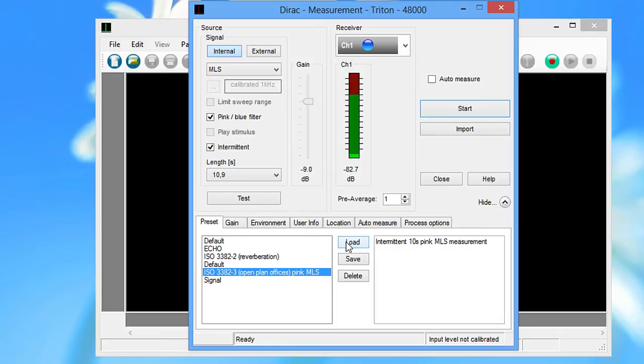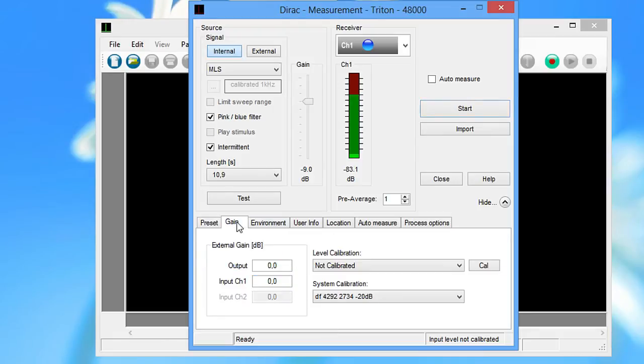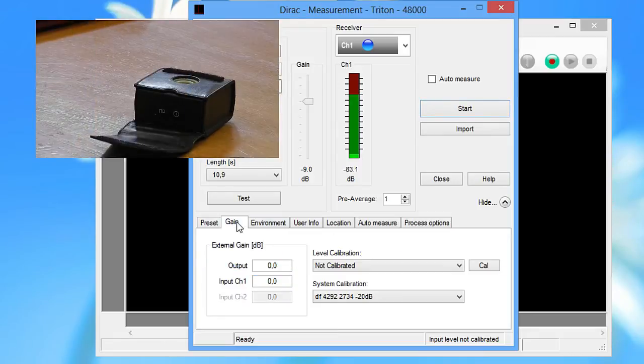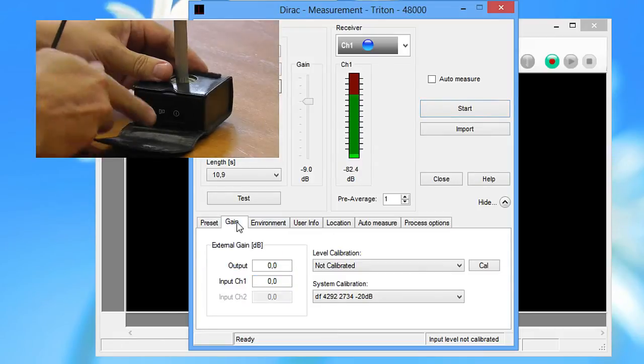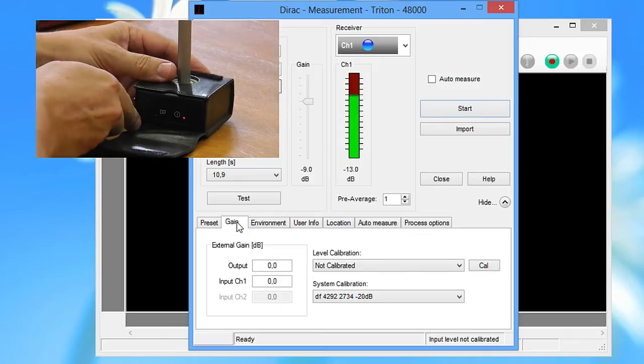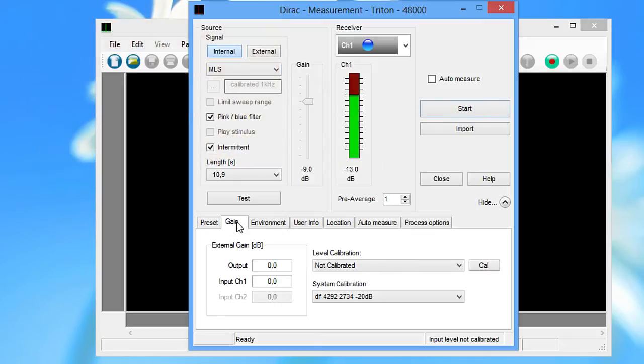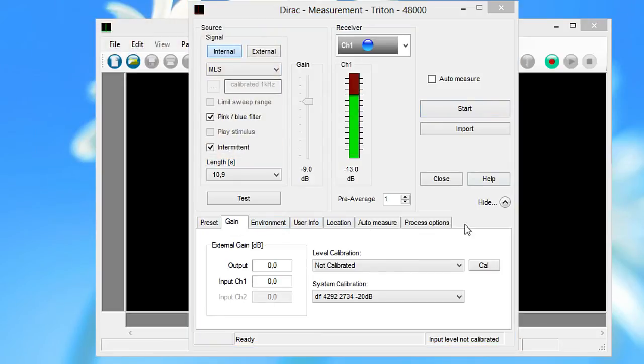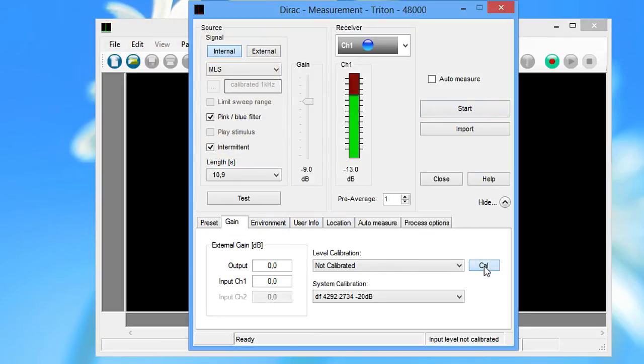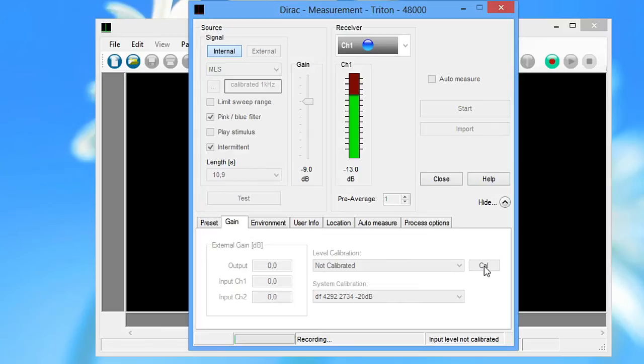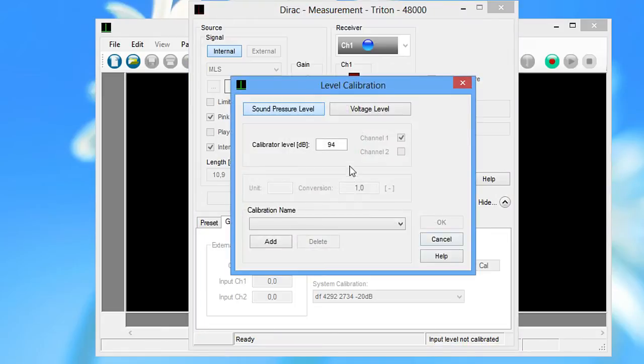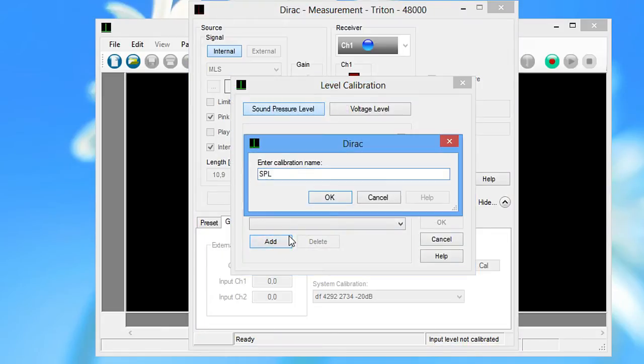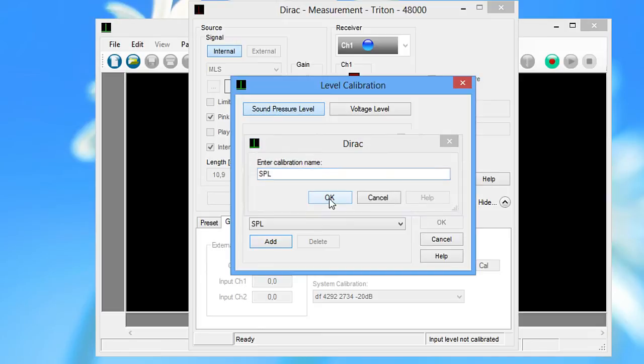First, you need to perform a level calibration. Insert the microphone into the calibrator and start the calibration on the gain tab. Enter the calibrator gain here and use the default name for the new level calibration.